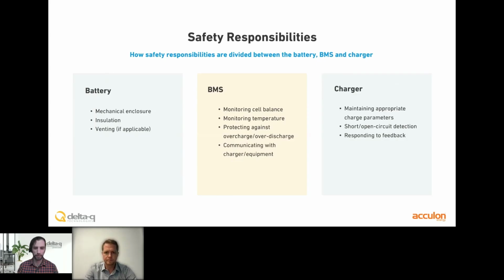The BMS, the battery management system, as Andrew touched on earlier, will monitor cell balance as well as temperature, making sure all the cells are healthy and at equal voltage. Often if you have one cell that's out of balance with the others, that can cause problems, potentially an imbalance in charge and long-term issues with the other cells. So having the BMS track the individual voltage of each cell is important.